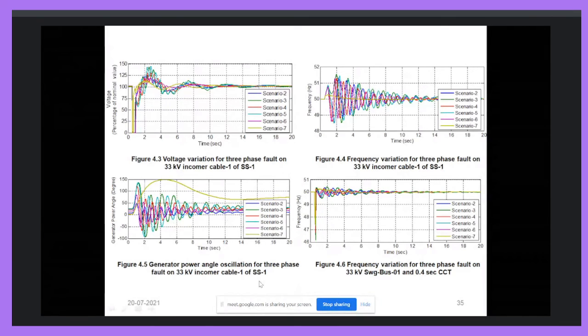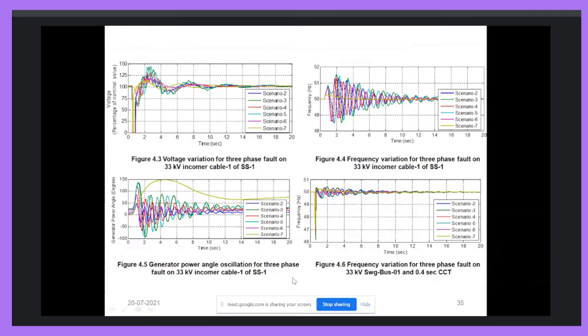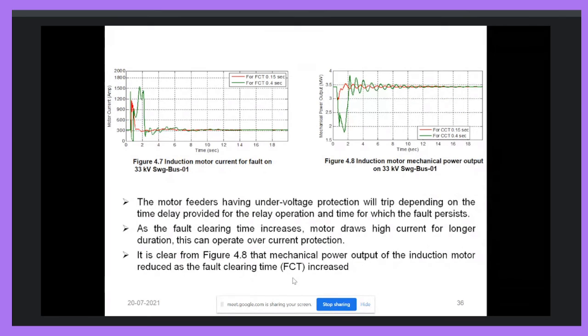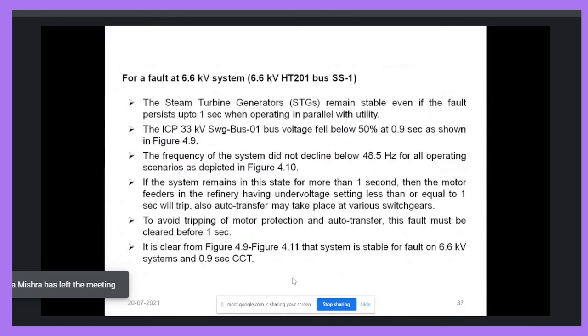Here you can see the generator power angle oscillation and frequency variation for the three-phase fault on the 33 kV switchgear bus. Now, as we discussed, whenever the fault occurred in the system, the induction motor output will also vary. The mechanical power output of the system will vary for different faults and different fault durations also. As the fault duration increases, the output of the motor will decrease. Here you can see with this diagram. So we want that the fault must be separated as soon as possible, and load generation balance must be maintained. For that we require a fast load shedding technique and fast protection system.